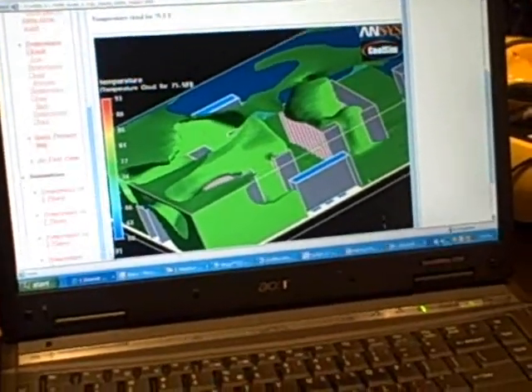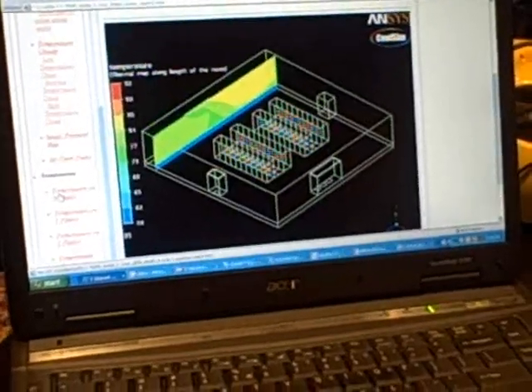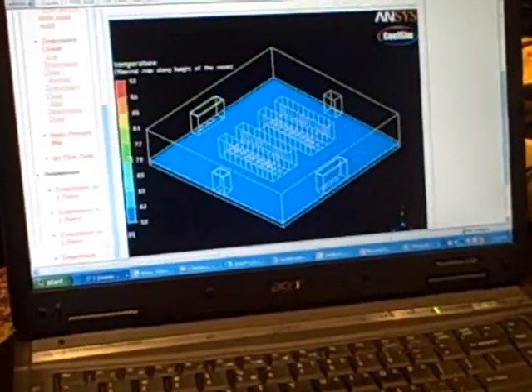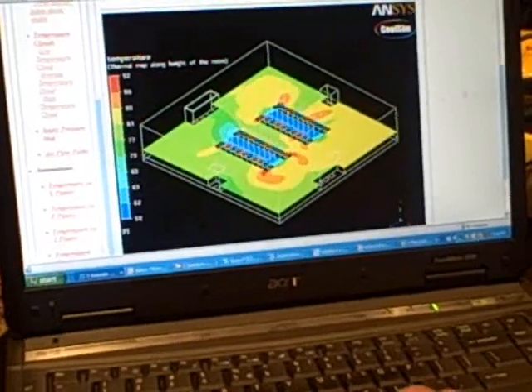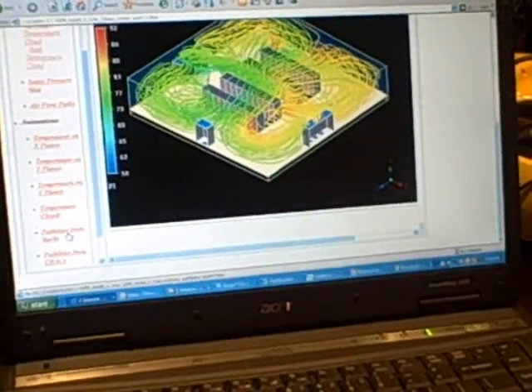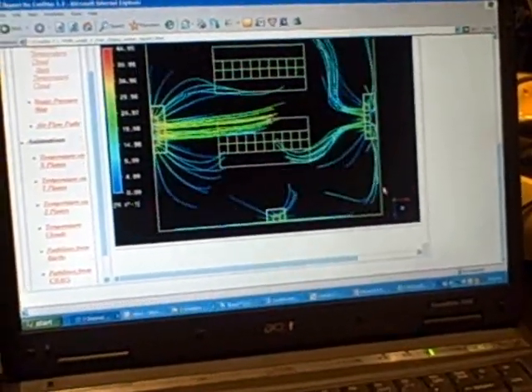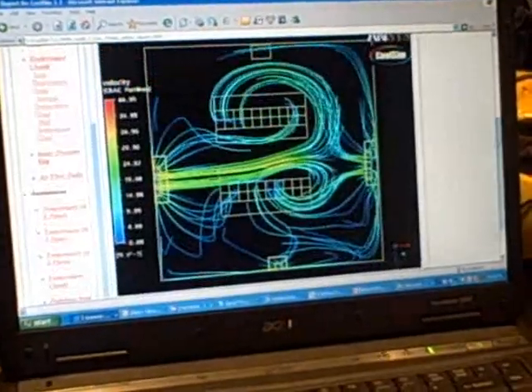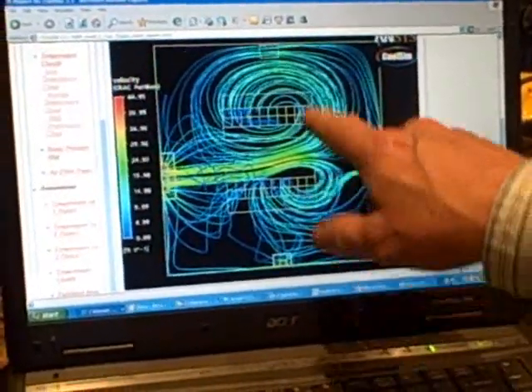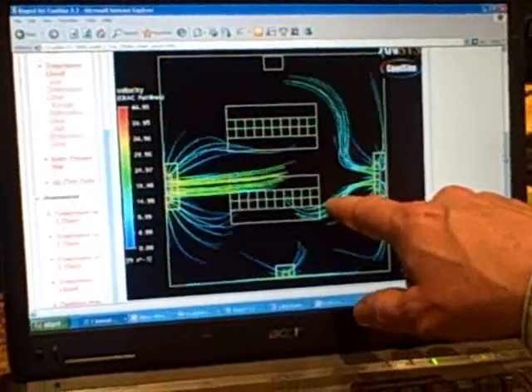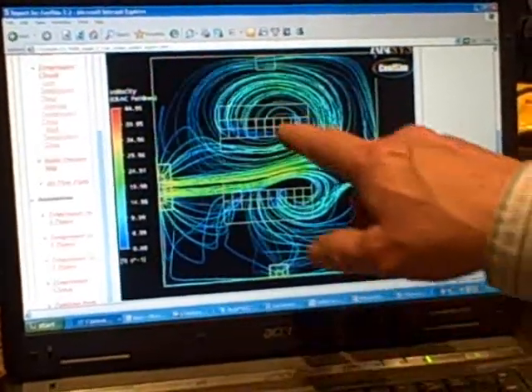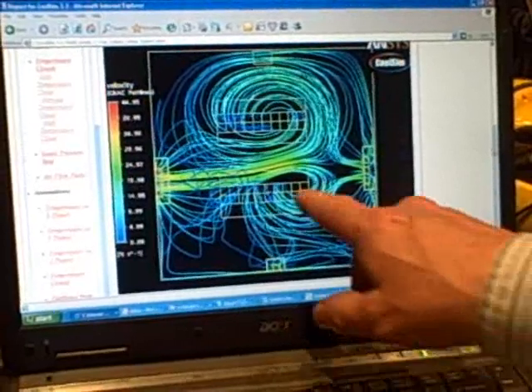I also have animations here in the X direction. I have animations in the Y direction. We have path lines from the racks back to the CRAC units, and from the CRAC units to the floor tiles. This particular image, you're noticing two vortices right here. This is a bad thing. This is going to mean very low pressure here. And you're probably having a flow problem in the system. In fact, that is where I'm showing hot problems right there.